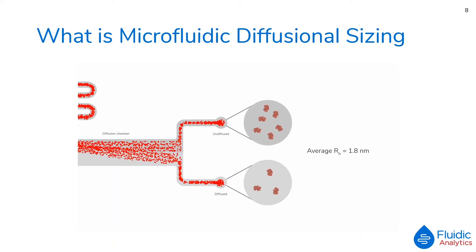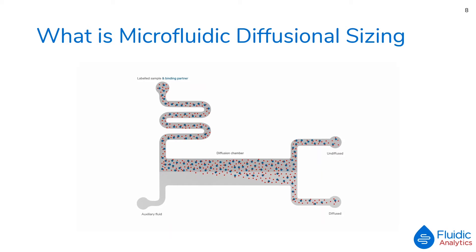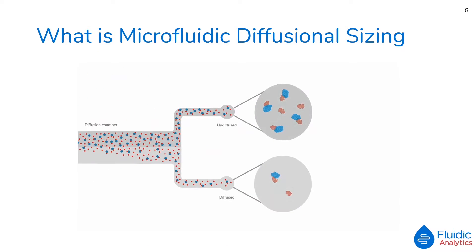The ratio of fluorescence between the two streams gives us the protein's hydrodynamic radius. The Fluidity 1W can measure this with proteins in buffer and in crude solutions like cell lysates or biological fluids, because only the labelled species is detected. If we repeat the test using a mixture of labelled protein and unlabelled binding partner, we can observe the degree of binding due to the change in size. Only species including the labelled protein are detected and measured. Titrating the binding partner against the labelled protein gives a binding curve and automatically generates a KD value on screen.